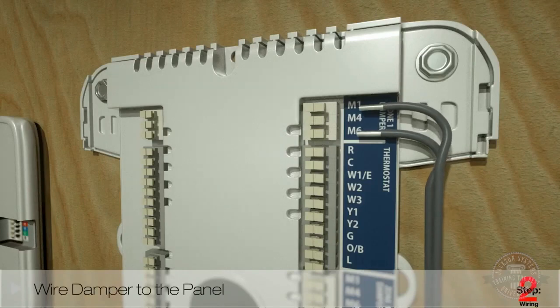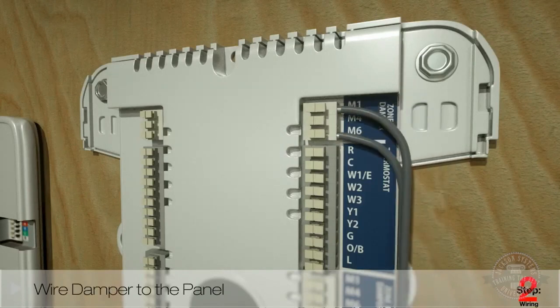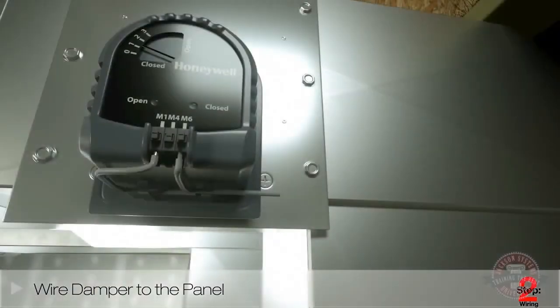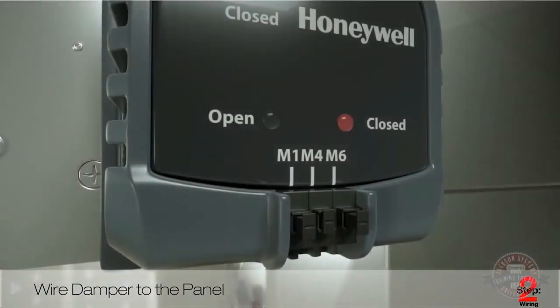Now that you have all the hardware selected and installed, it's time to move on to the wiring. Start by wiring your dampers to their corresponding zones on the TrueZone panel. The TrueZone dampers operate on 2 wires, wire M1 and M6 to the corresponding zone on the TrueZone panel. Use the optional M4 terminals to enable the green open LEDs. For access, simply break off the plastic tab.